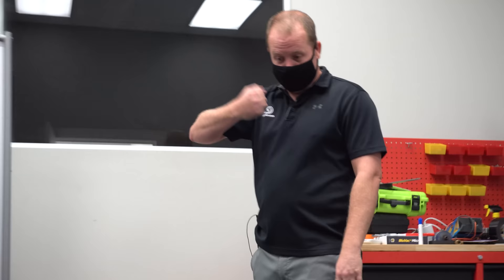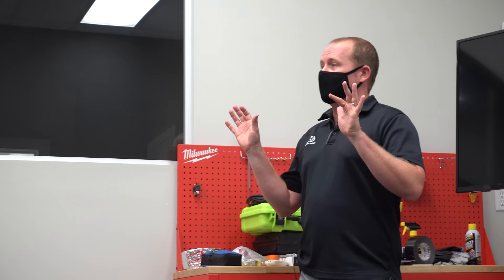As we've talked about on service calls, that means taking your flashlight and looking down that drain, making sure it is clean. If it's not, quote a drain cleaning. A drain cleaning is more than just a drain line cleaning — it's a condensate assembly cleaning. It includes cleaning the drain pan and being really thorough. Most of you already know this stuff, but I want to reiterate: cleaning is important. In some ways, a good technician is a good janitor. We've got to be good at cleaning — it's part of our job. We've got to embrace that.